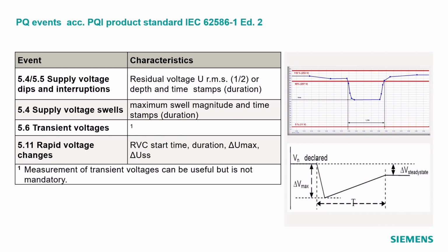And it's similar for the rapid voltage changes, but rapid voltage changes do not cross the plus minus 10% voltage band. They always stay in the plus minus 10% voltage band. They are mostly caused by switching of big loads. So the voltage is going down by 3 or 5 or 7%, but not by 10%. And the voltage is coming back slowly and is stabilizing on an old declared voltage or on a new voltage level, which is characterized by the delta U steady state then. It's a quite new definition, and it's only observed and logged, but not evaluated clearly in the evaluation standards.